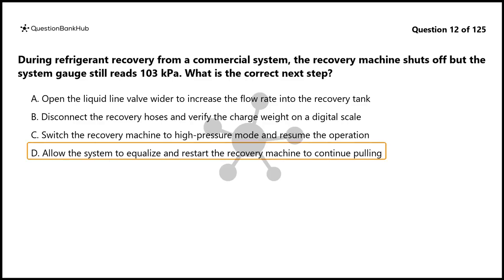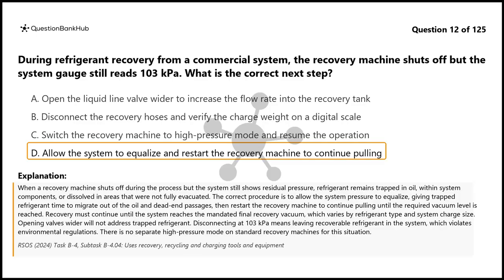The correct answer is D. When a recovery machine shuts off during the process but the system still shows residual pressure, refrigerant remains trapped in oil, within system components, or dissolved in areas that were not fully evacuated. The correct procedure is to allow the system pressure to equalize, giving trapped refrigerant time to migrate out of the oil and dead-end passages, then restart the recovery machine to continue pulling until the required vacuum level is reached.